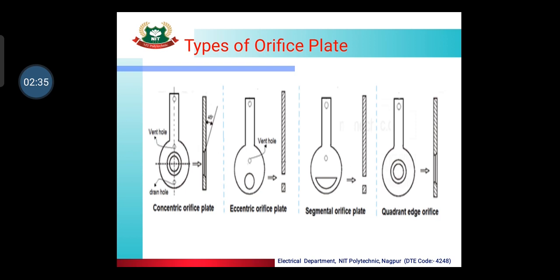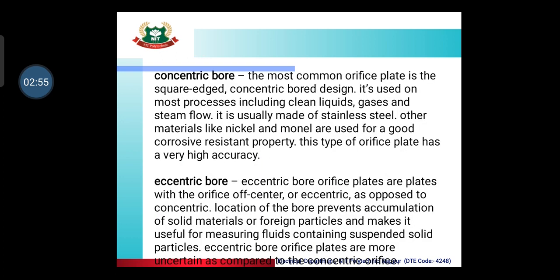This is the orifice plate — a thin layer with a hole drilled in it. There are four types of orifice plates: the first is the concentric orifice plate, the second is the eccentric orifice plate, the third is the segmental orifice plate, and the fourth is the quadrant edge orifice plate. The concentric bore is the most common orifice plate — it is a square-edged, concentric bored design used on most processes including clean liquids, gases, and steam flow. It is usually made of stainless steel; other materials like nickel and monel are used for good corrosion-resistant properties. This type of orifice plate has very high accuracy.